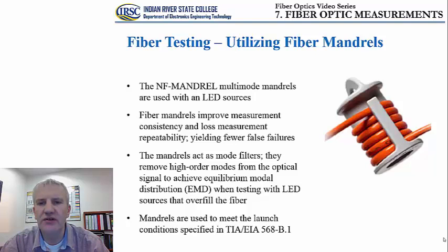If you wind the optical fiber on these plastic holders called fiber mandrels, they act as mode filters. In other words, they remove higher order modes from the optical signal, and by doing that you achieve equilibrium modal distribution when testing with LED sources that overfill the fiber. If you are using an LED as a source, you know that the LED spreads light, it diverges, and it may overfill the fiber and create certain higher order modes. So using mandrels reduces the presence of those higher order modes that create certain issues during the measurements.